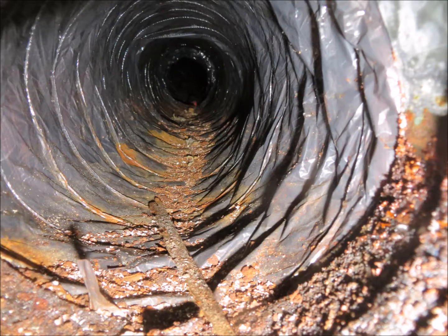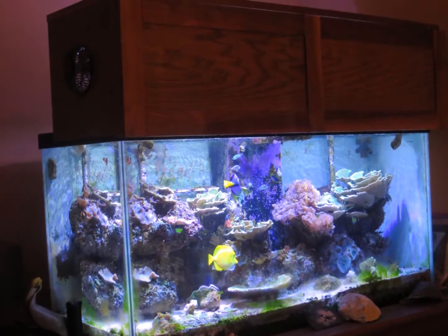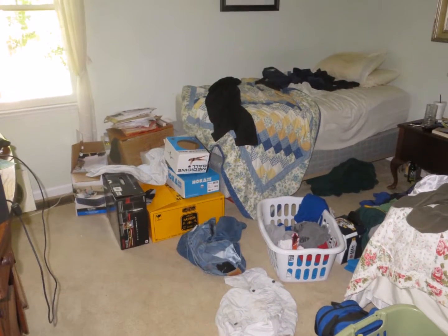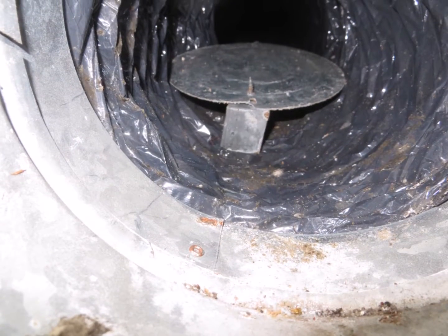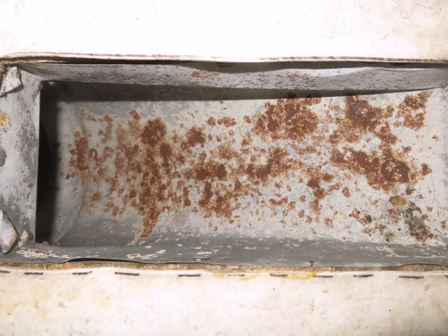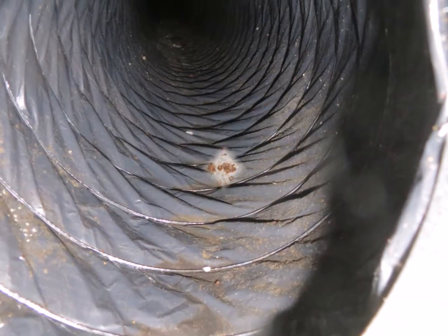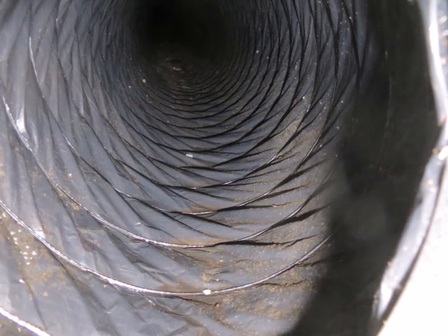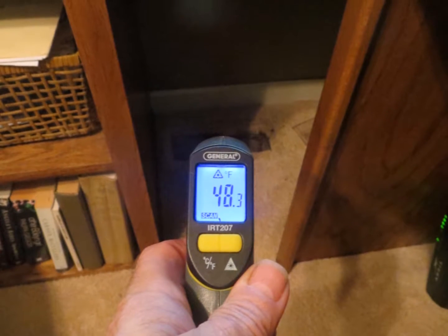That's a highly corrosive material that would create that much rust and send that rust into the air ducts. It's suspect that this fish tank is the source of that corrosive material, because in the other rooms upstairs, the ducts do not look nearly as bad. There is debris and suspect mold within them, some oxidation, which is normal with the duct in the bathroom. But again, apart from an oily substance and light layer of debris, the ducts do not look the same.